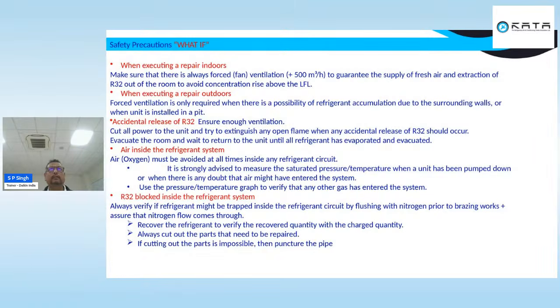Because our compressor cannot compress air or oxygen, again it will create pressure, and there is a possibility that an accident will take place. It is advisable that the unit has been pumped down. If you have any doubt, first run the system for at least 5 to 10 minutes, and after that start the pump down immediately. First you should check whether the system has proper pressure or not.